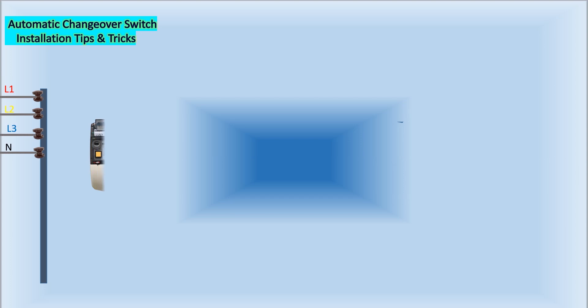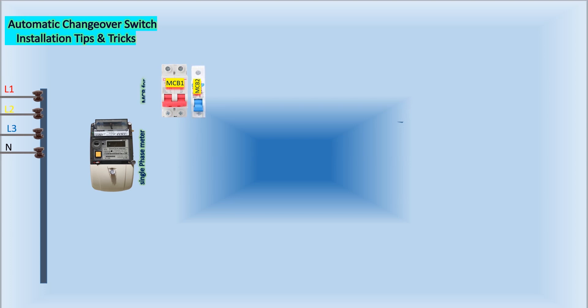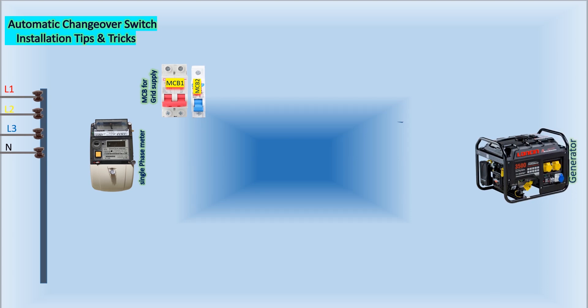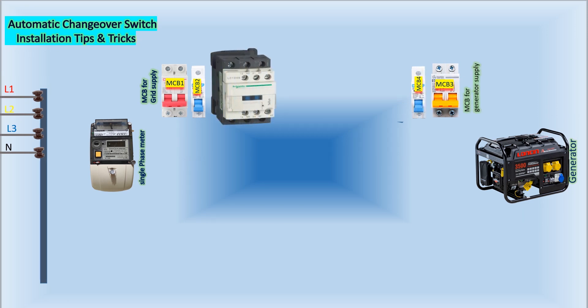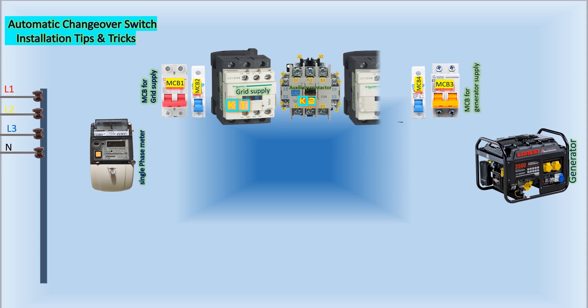The ATS consists of several components. These include an energy meter, a two-pole MCB for the grid supply, and a single-pole MCB for control. For the backup generator supply, a two-pole MCB and a six-amp single-pole MCB are used for the power and control circuits, respectively. Additionally, three contactors are employed in this changeover switch: K1 for the grid supply, K2 as an auxiliary contactor, and K3 for the generator supply.